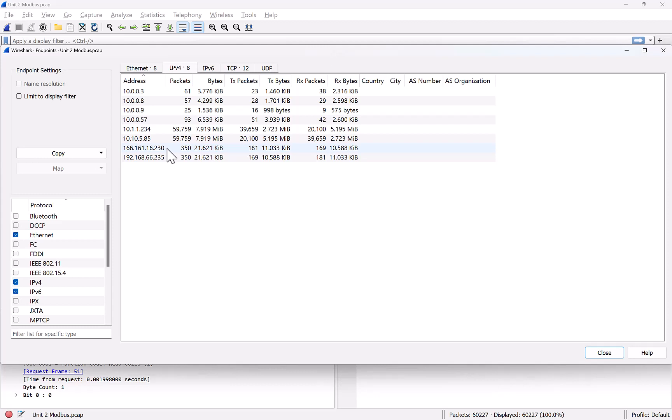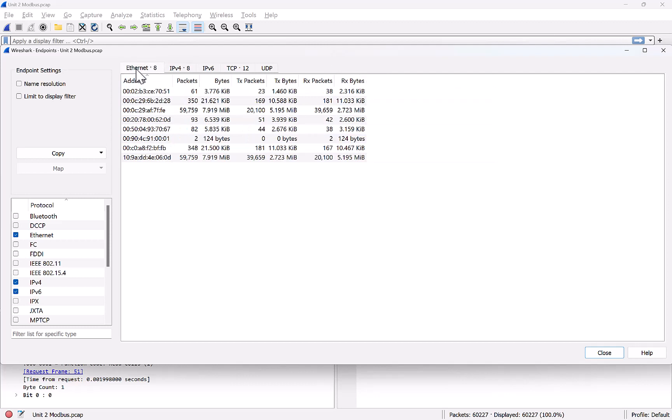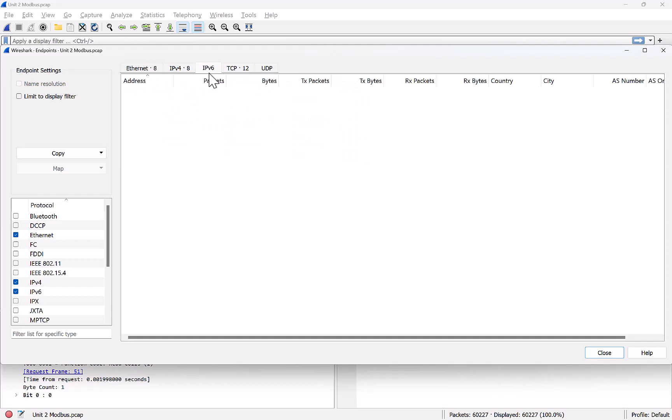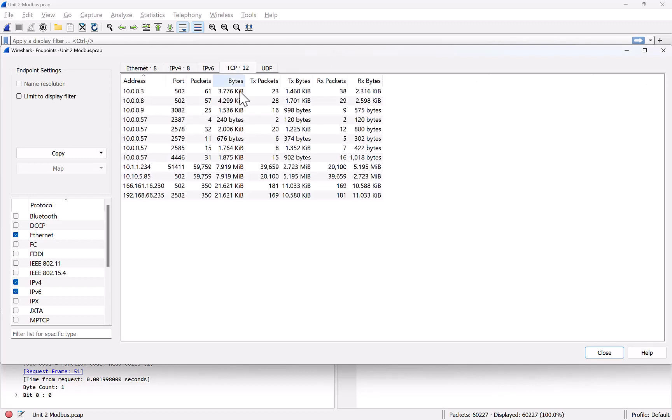But that's one way where we can see what hosts are in the environment. And then you can also get an understanding of how much information is being sent between these. A lot of control system environments do not send a lot of traffic. You might have one command that goes between two hosts every week or once a month. They're not, for the most part, very talkative. When you see a lot of talking hosts, that could be things like maybe data historians that are transmitting or transferring process data from point A to point B.